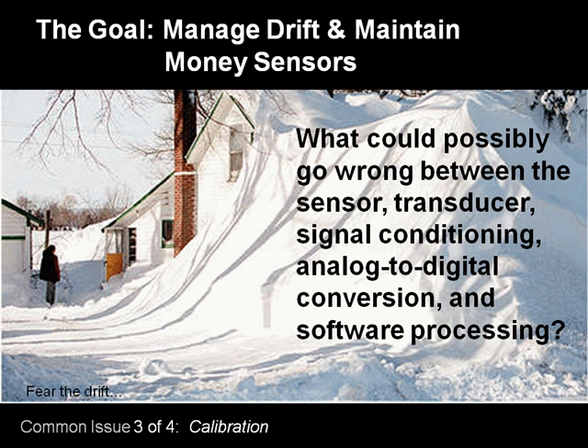So you have a bunch of different kinds of sensors. You ought to have them looked at once a year. Have your control contractor come in and take a look. And as a commissioning agent in a high-performance building, I would like to see a test hole put next to that temperature sensor, so when the balancer comes in, he can plug in there, just feeding the calibrated instrument right next to it. Now you're reading from the same place every time, and if your operators are doing your own calibration, they're reading it with the same instrument. So you collect data at the same data location every time. I suggest that pretty much every week.